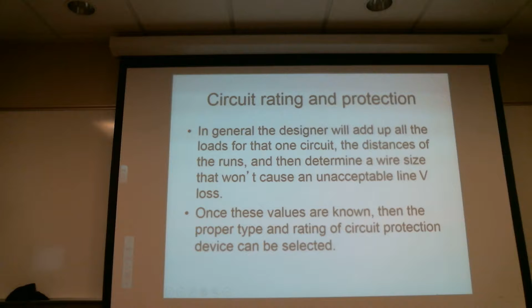The circuit protection device is really the amperage. The choice of circuit breaker or fuse is kind of up to you. They both have their pros and cons. In the case of a fuse, particularly a fast blow fuse, you can get a fast blow fuse to react very, very quickly. I can make a digital circuit sensing that will trip quicker, but it'll be a pretty darn expensive thing. The standard typical circuit breaker works off of an element getting hot, getting heated up to the point that it eventually trips. And they're pretty casual.